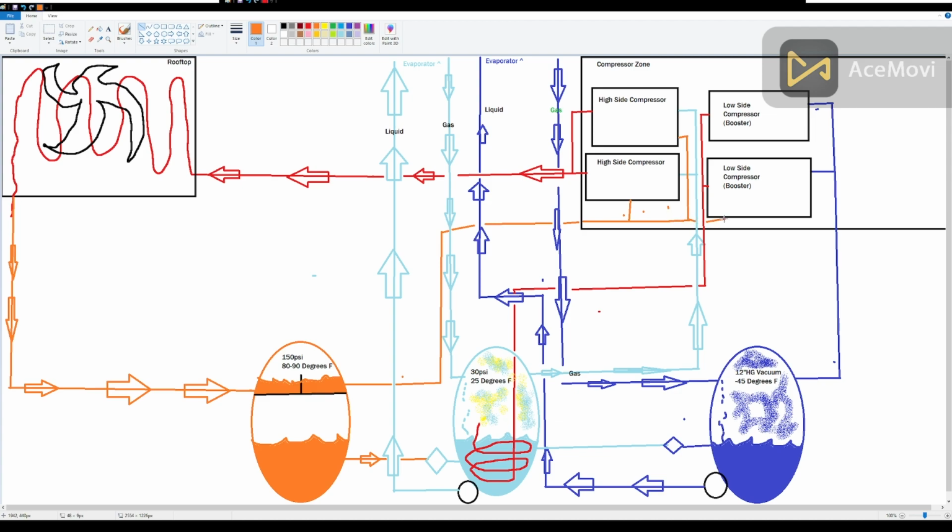And it's going to provide cooling for your compressor's oil. You might say, well, I thought that was like 90 degrees in there. Yeah, well, your compressor's oil is like 200 degrees. So it's cooling it. And I hate showing this on a diagram because it just adds more clutter to the piping, and it's useless to know this. There's almost no reason you'll ever touch a thermosiphon because it either works or it doesn't work. However, it would not be a complete image if I didn't show you that this is what a thermosiphon is. This is what that bisection is doing. And there will be a thermosiphon return coming back. I'm not going to draw that. I think you get it.